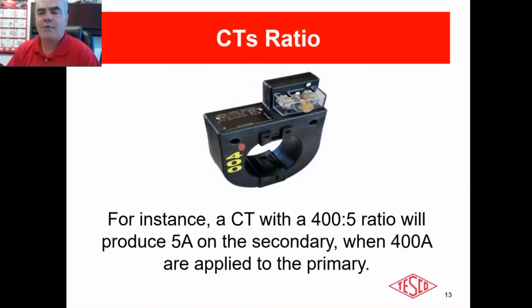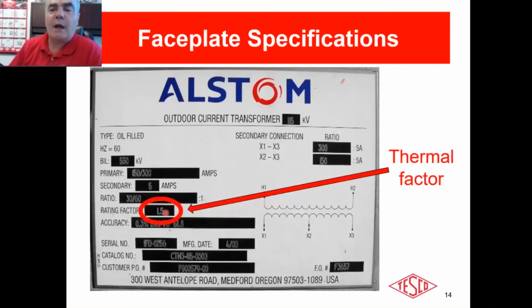Well, how would I catastrophically fail that transformer? One way is to overheat it. As I overheat it, those coils want to do what? They want to expand. Well, there is no way for them to expand because they're fully potted, all right? There's no way that they can expand. Now, as they expand, if I really overheat this, eventually it's going to crack that potting. Once the insulation begins to break down, that potting begins to break down, now I could have a turn-to-turn short in that transformer, and I will have a problem. That transformer will fail. So the thermal rating factor is important. That tells me how high I can use.